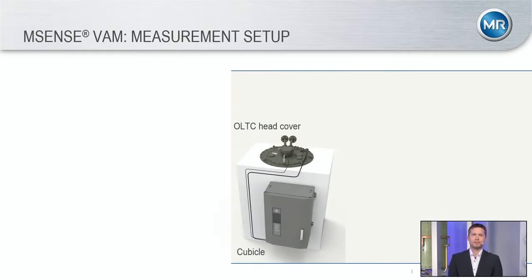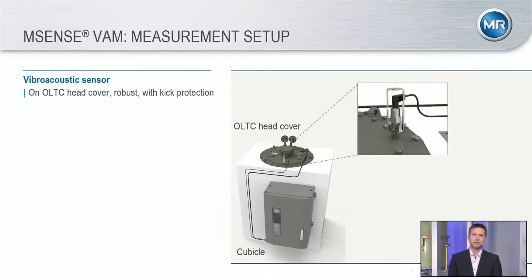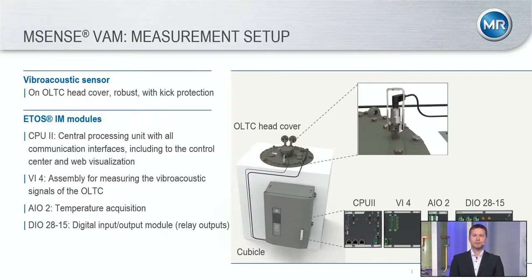The installation of the mSense VAM is very easy. By removing a bolt from the head cover, the mSense VAM sensor can be installed on the head cover. It is a stainless steel holder for the sensor, very robust for temperatures and environmental influences. The connection from the sensor to the motor drive unit or to the ETOS is done with one cable, connected to a special measurement card — we call it the VI4 card, which is especially developed for these vibroacoustic signals. The CPU is normally already there with the ETOS, so there is no need to install a second CPU card; the existing CPU card can be used.